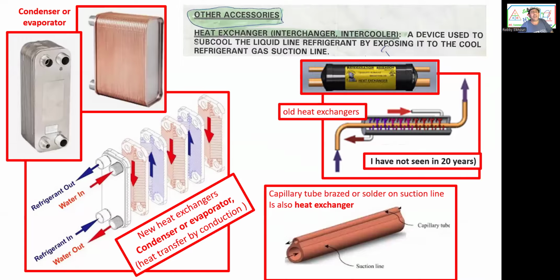And we also have the heat exchanger. When we talk about the heat exchanger nowadays, it's a metal plate like this, with freon in and fluid out. This is the new heat exchanger style. It's a condenser or evaporator, cooling or chilling water or fluid, or in some cases, in the new hybrid variable frequency drive air conditioning systems, actually using CO2 also.